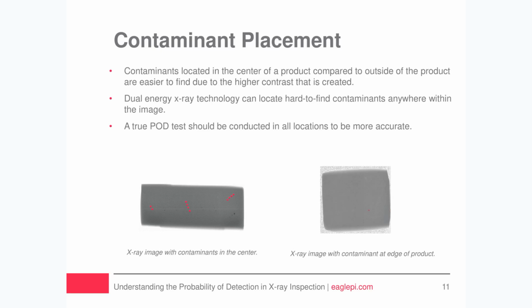Looking at the two images in the slide, they're both obviously blocks of cheese, which are typically very thick, very dense. This means that the probability of detection and contaminant detection levels vary across the thickness of the product, as previously discussed. This means that to effectively provide specifications within this type of application, contaminants must be seen at the top, middle, and the bottom to factor in the varying magnification levels throughout the whole of the product.